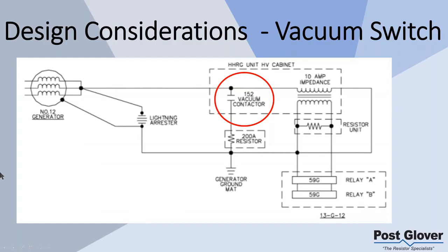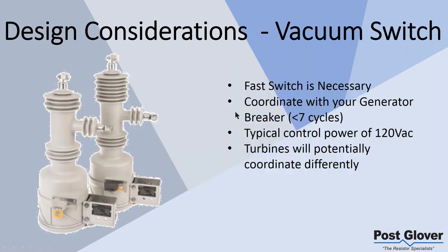So here's an example of a generator that's using different components, one of which is a vacuum switch. This is what isolates that LRG. You're going to have a high-speed disconnect essentially. You're going to want to match your generator, your main switch. So you're basically going to want to coordinate with your generator, usually at less than 7 cycles. So it's going to have to operate fairly quickly to operate completely within that time frame.